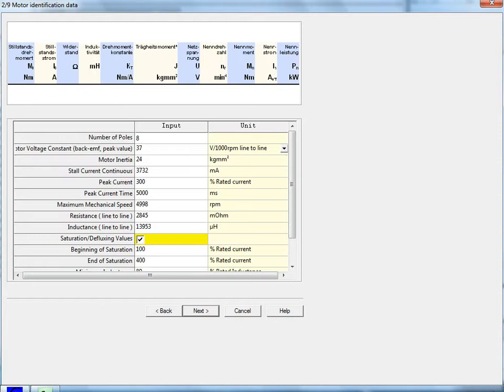Time at peak current is how long the motor can handle the peak current in milliseconds. The maximum mechanical speed is typically the bearing limit, but you can also set it as a maximum speed for the feedback device. The resistance is in milli-ohms, and the inductance is in micro-Henrys. For saturation and defluxing values, leave this unchecked for permanent magnet synchronous motors.